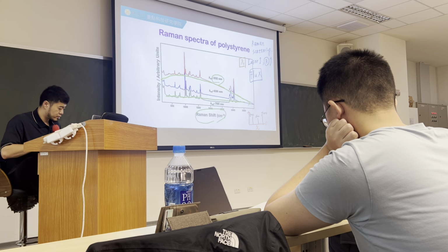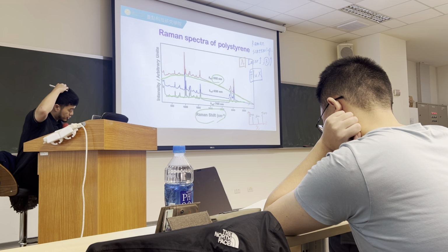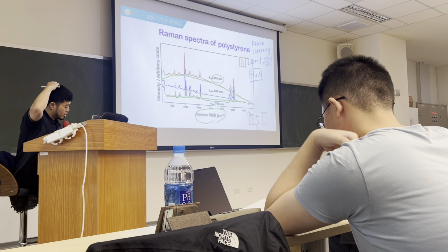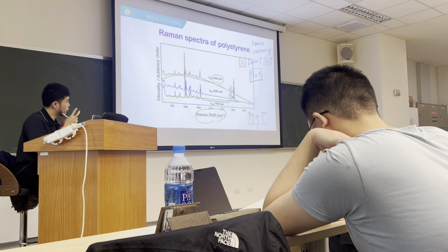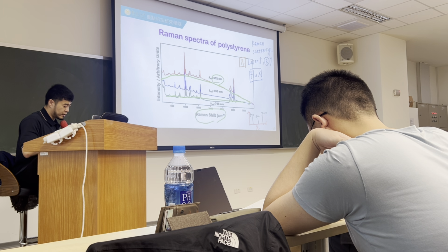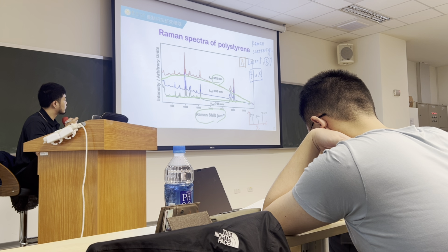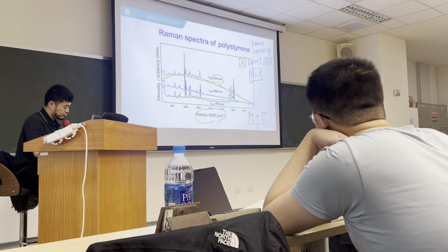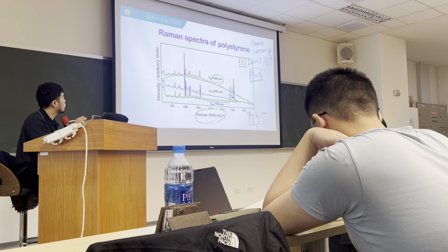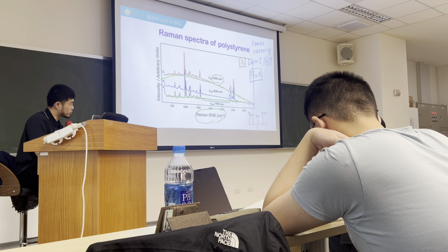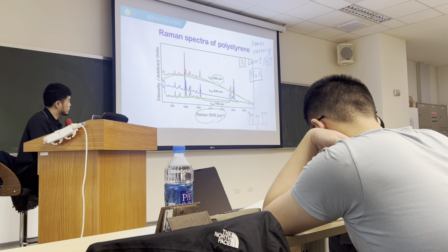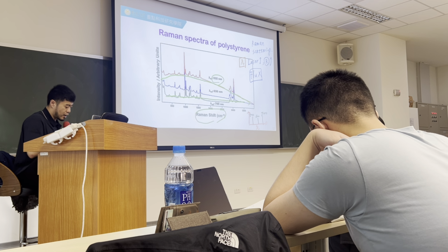Based on this, you can understand why, if you check some Raman equipment, most of the time we assemble more than one laser light source on the Raman spectrometer. Because if you have different materials, the fluorescence will be located at different wavelengths, so you commonly use different lasers to avoid the fluorescence influence.